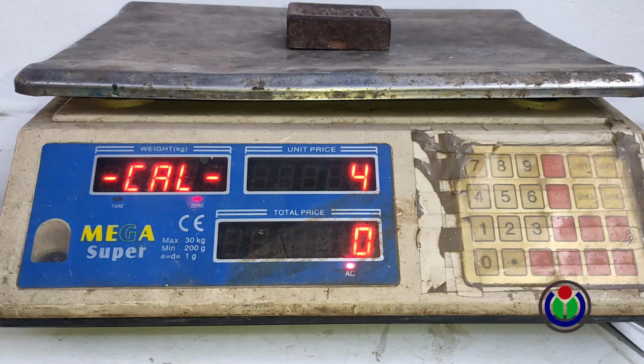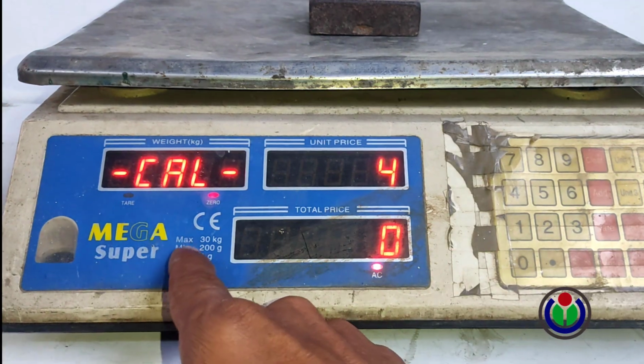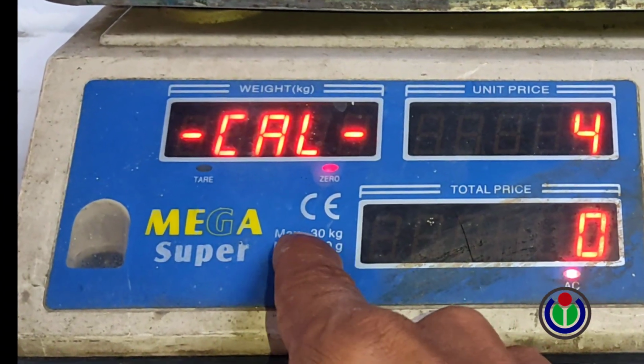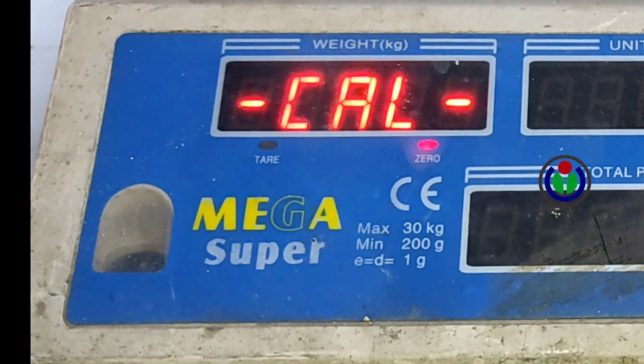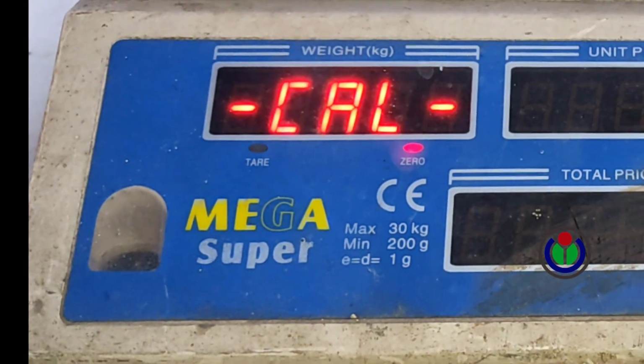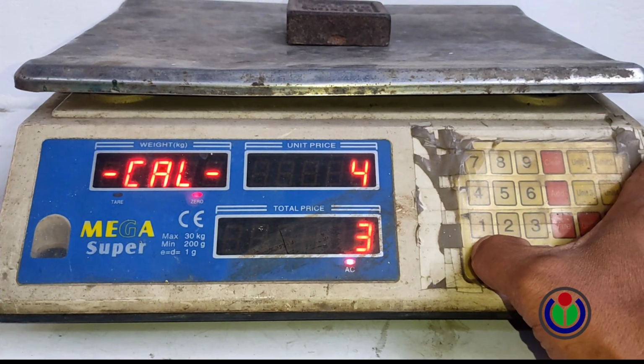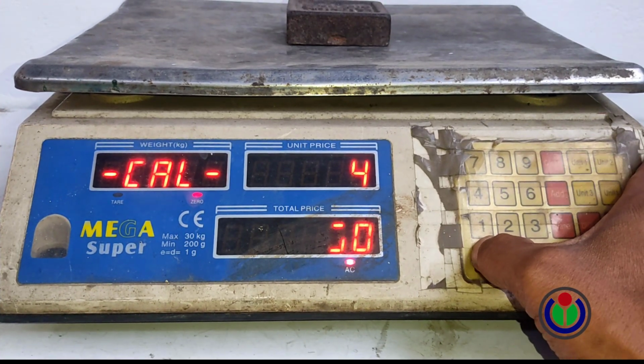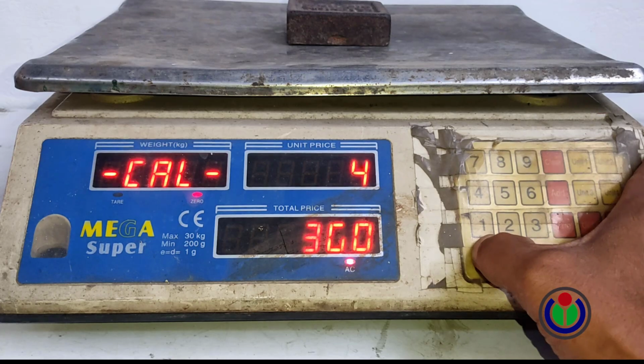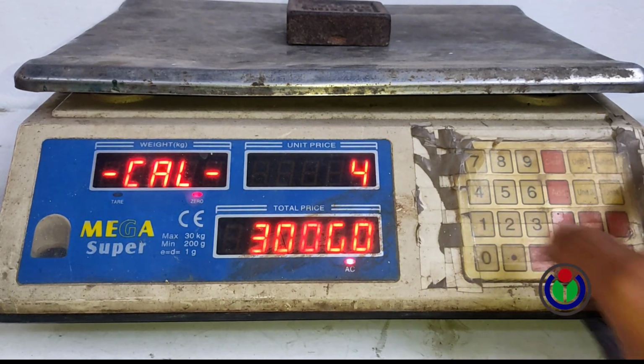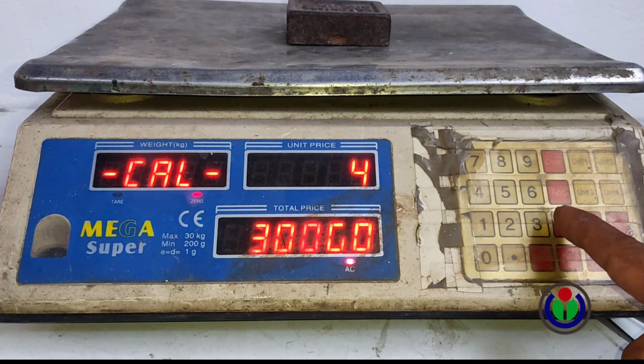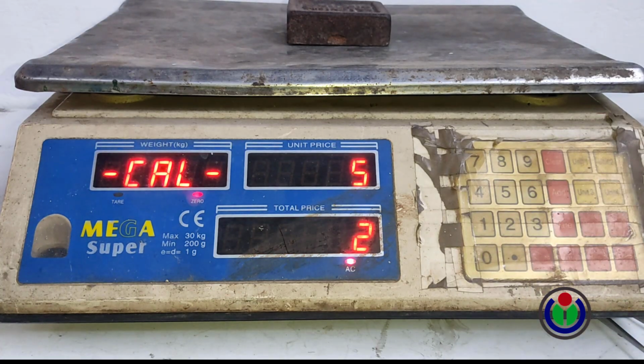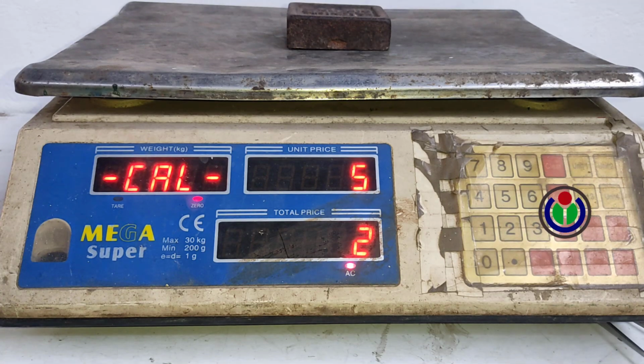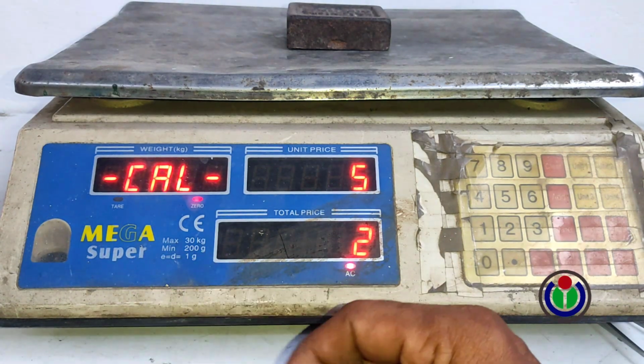Step 4. The maximum amount of objects that the weighing machine can weigh at a time is usually mentioned on the cover. In this step, I entered the maximum weight capacity of this scale, 30 kilograms, in grams. 30 kilograms in grams is 30,000. I pressed 30,000 and pressed Tare once. Step 5. In this step, there may be some difference in weight, which is plus or minus 2 grams. I kept the default 2 grams and pressed Tare once.